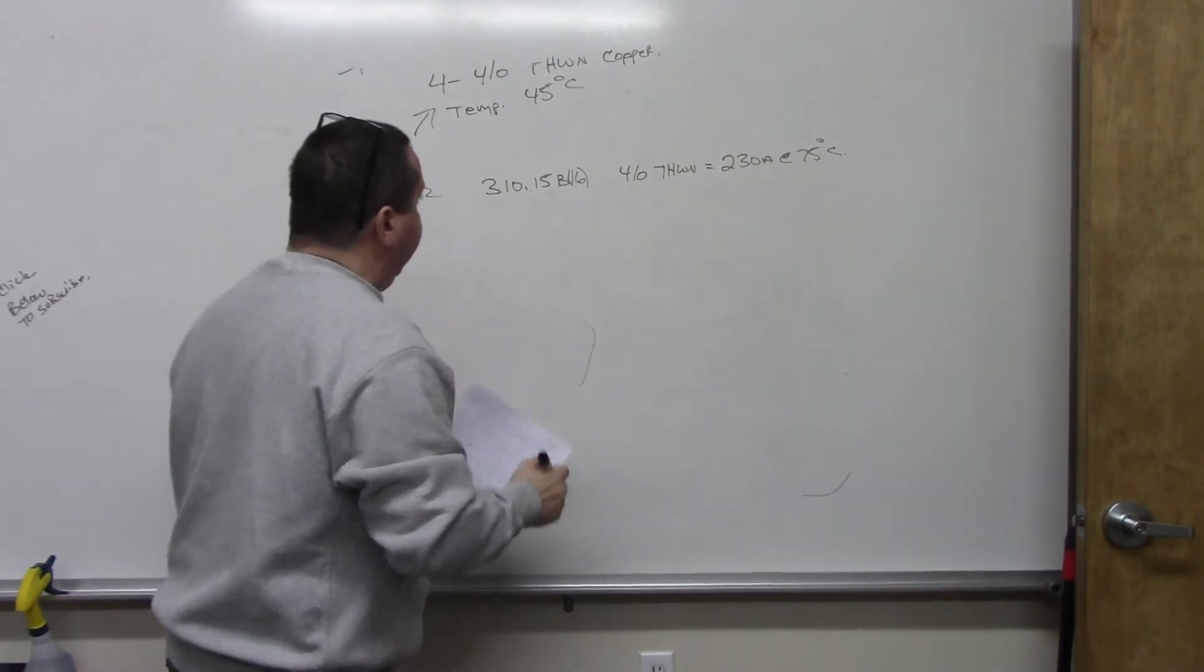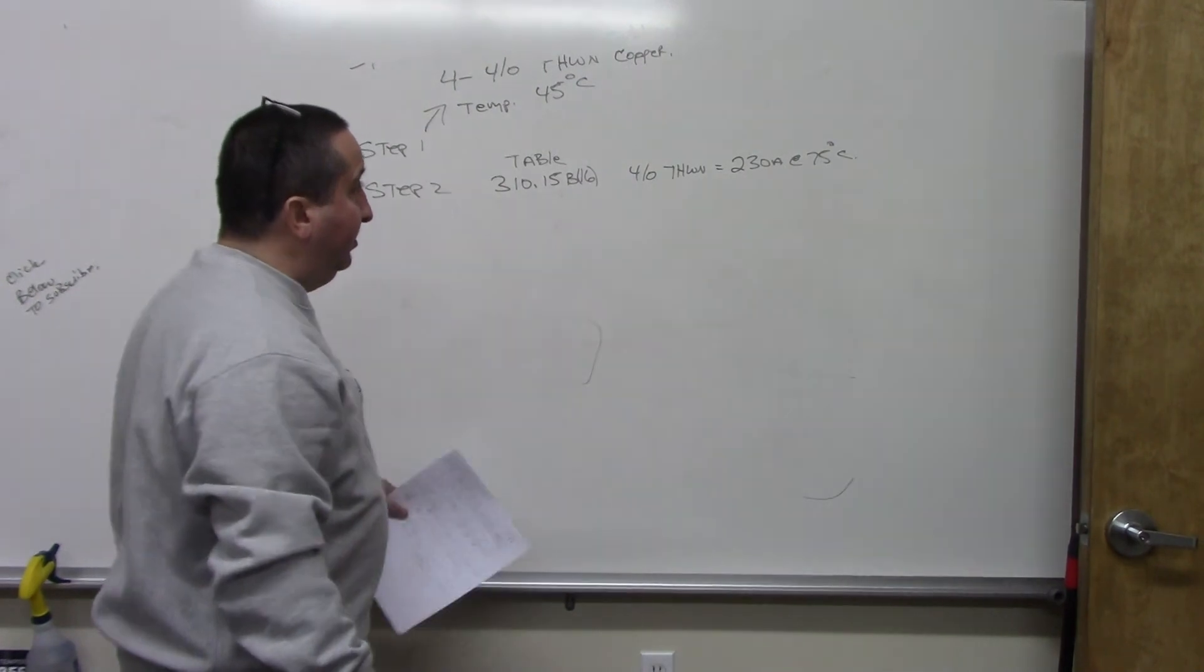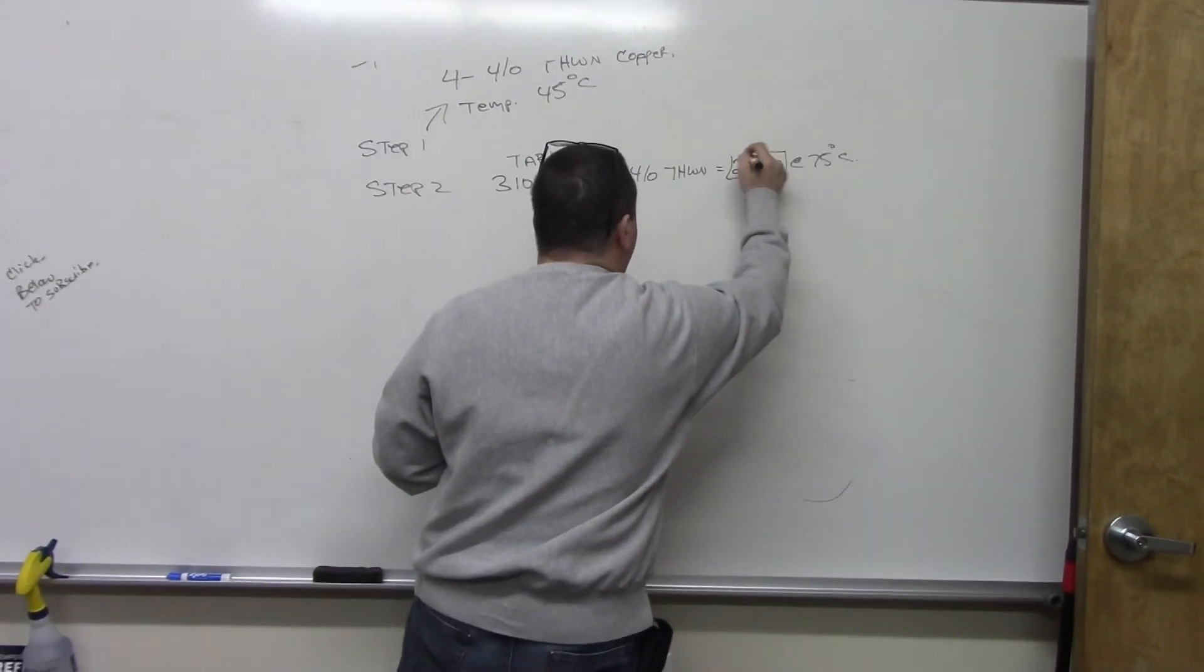we find out that a 4/0 AWG THWN is equal to 230 amps at 75 degrees Celsius. That's the table you would be going to, and it's copper. So this is the answer right here, 230 amps.